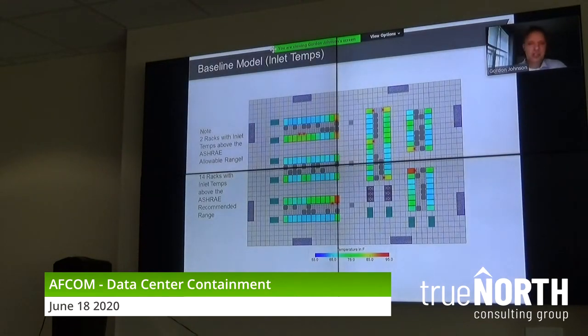If you look on the slide, wherever you see the red dot, it's color-coded. The red dot represents servers that have temperatures above 80.6. The color is the highest temperature at any place on that rack. So, very common. Again, you're going to see overheating at the end of the aisles. Hot air recirculating around the end, like we saw in that video a moment ago, and also in the middle too. You'll have the hot air coming over the top of the racks. We'll use the expression licking the first 5 or 10 U, causing overheating there.